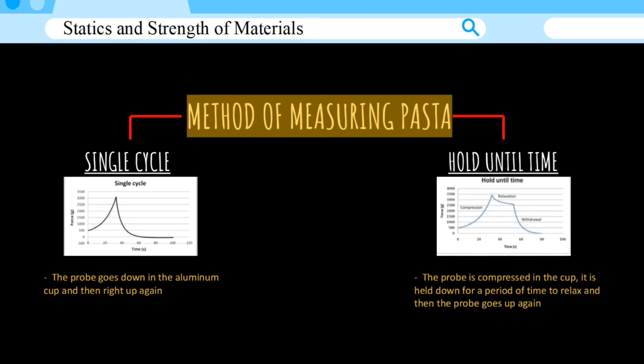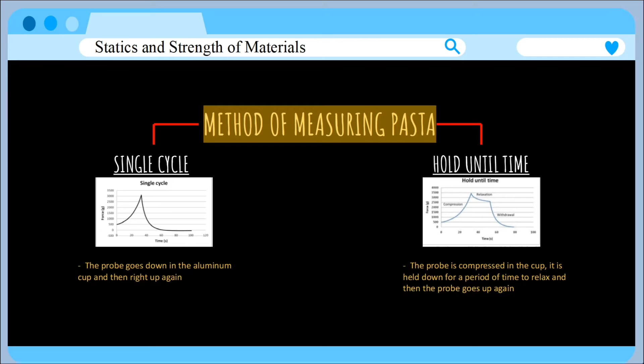So, what is the difference between the two methods? Basically, single cycle and hold until time differ in procedure and observation that is taken. As for single cycle, the probe goes down in the aluminium cup and then right up again. While for the hold until time method, the probe is compressed in the cup and it is held down for a period of time to relax, and then the probe will go up again.